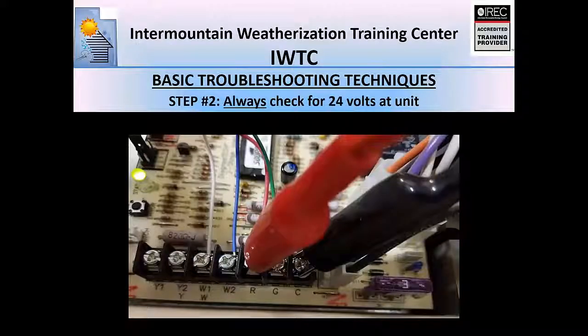So the first one was about checking for voltage and why non-contact voltmeters are not a good tool to use. You should always use a regular voltmeter, check for 120 volts at the unit. The next step I always do is I check for 24 volts. Now I'm going to show you how to check for 24 volts at the furnace circuit board. This simple test is another way to determine if you have correct mainline voltage to the furnace.